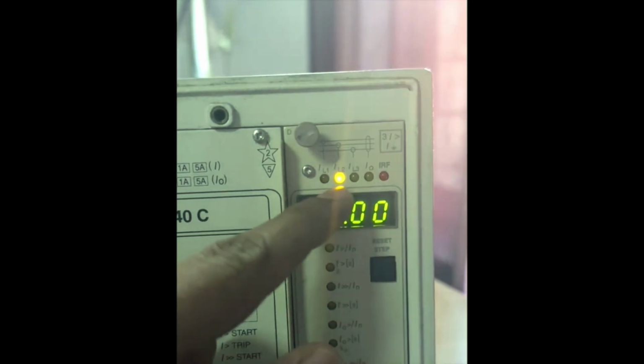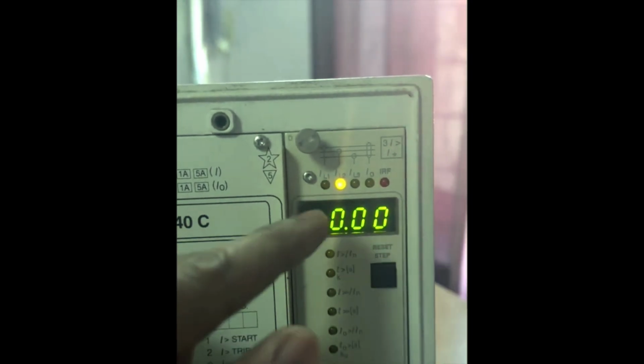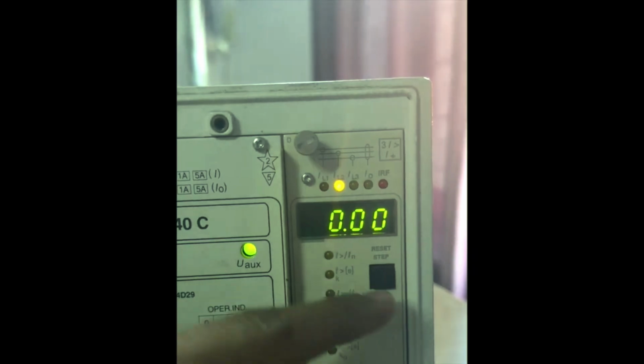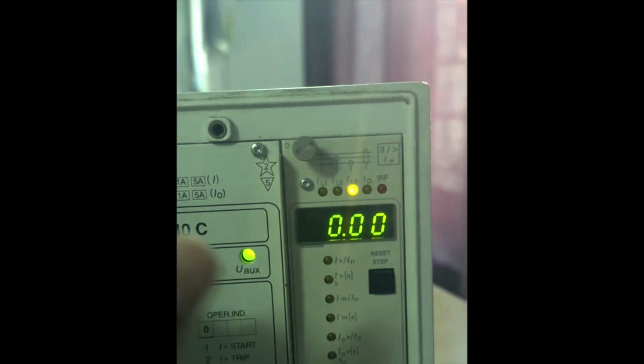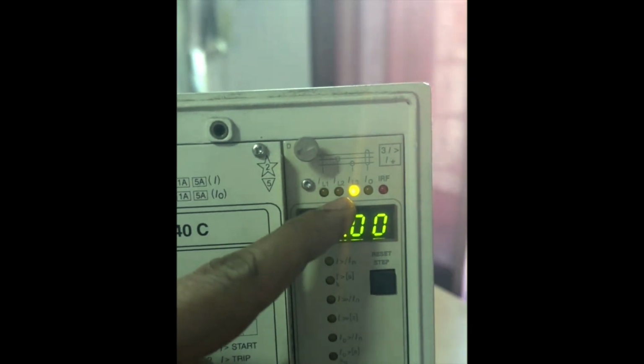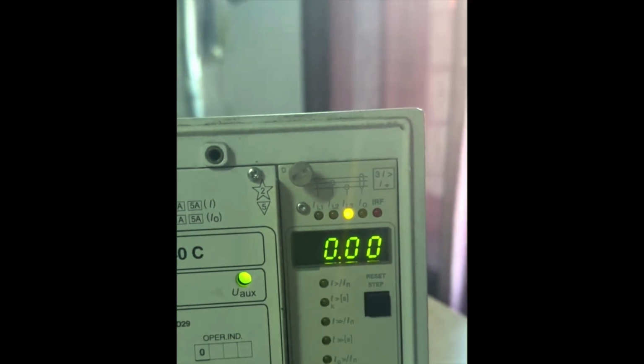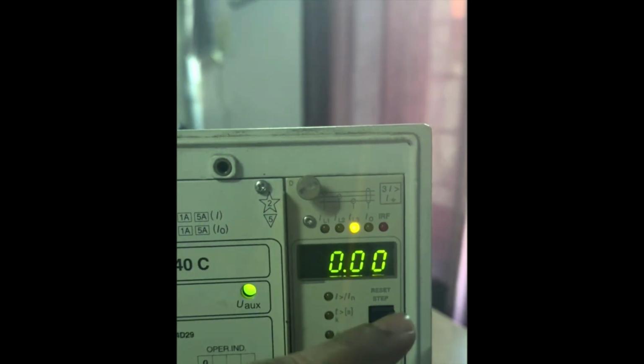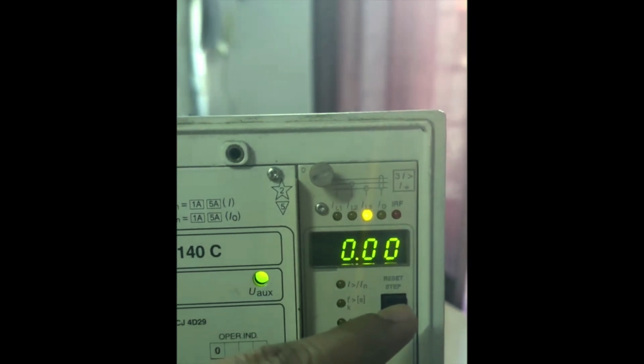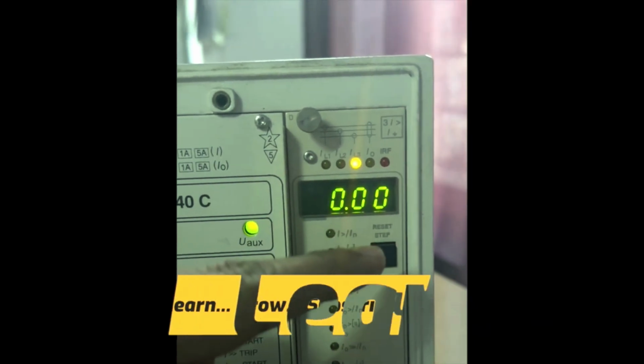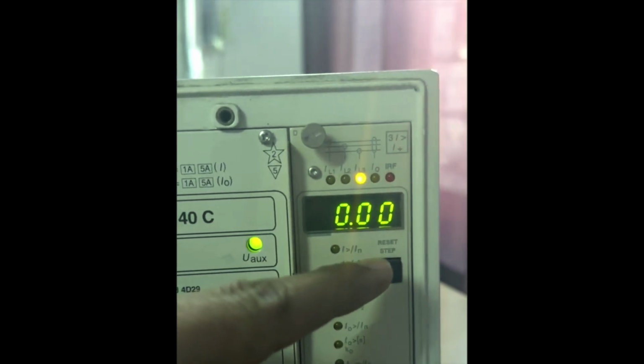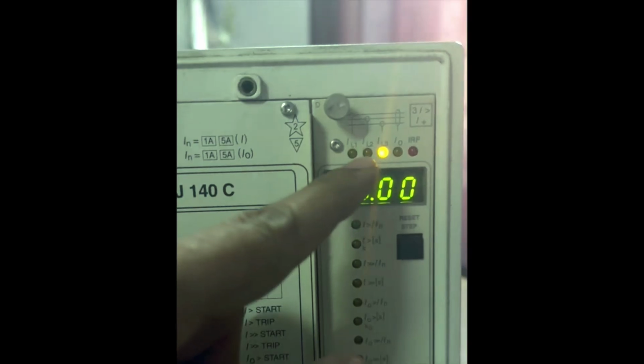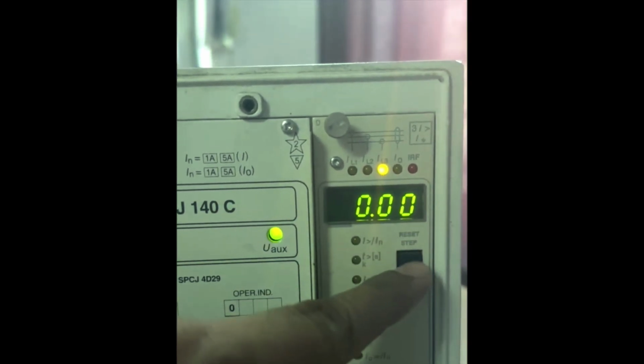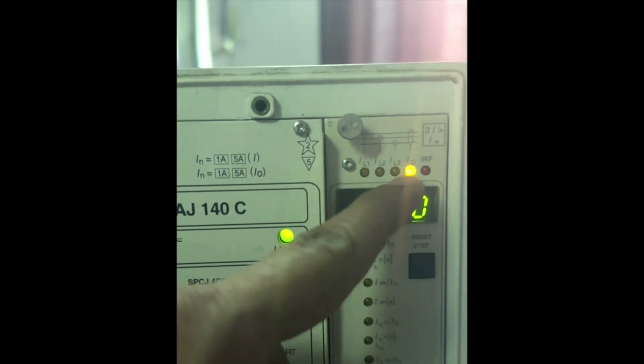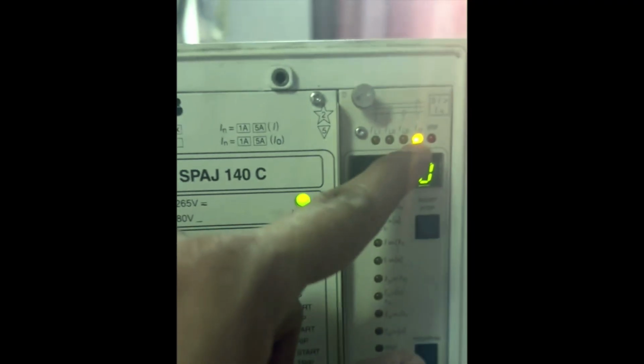If you press it again, IL2 will come on. This means the current on the Y phase, which is the running current. IL3 means the current on the B phase, which is currently 0 because this relay is not connected to the supply. But you have to assume that it's there. So friends, R phase, Y phase, B phase, and then if you press I0, the 0 means the current in the earth. Okay?